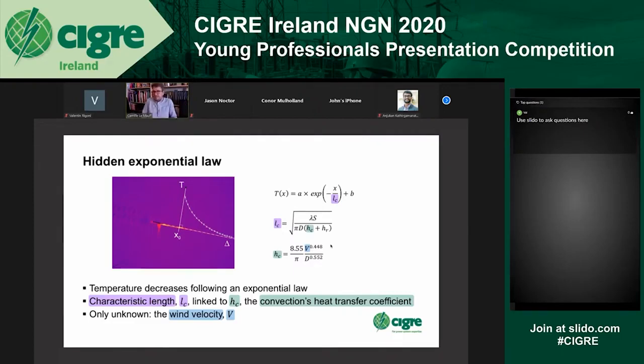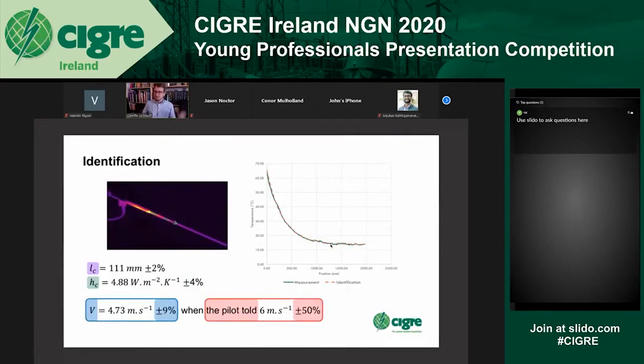Let's do it. I'm taking a dead-end joint that is overheating, and this is the infrared image on the left side. You can see that, as predicted, the temperature along the conductor is not uniform. What I'm doing is extracting the temperature along the conductor. This is the green curve on the right figure, where temperature is a function of the position along the conductor.